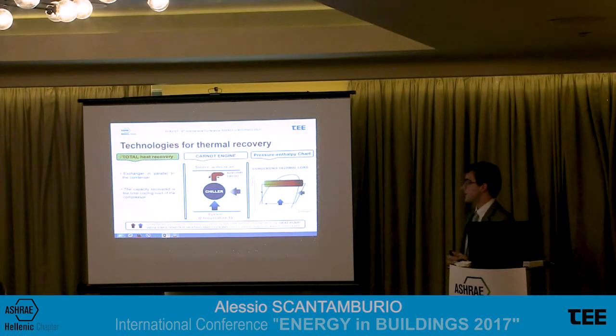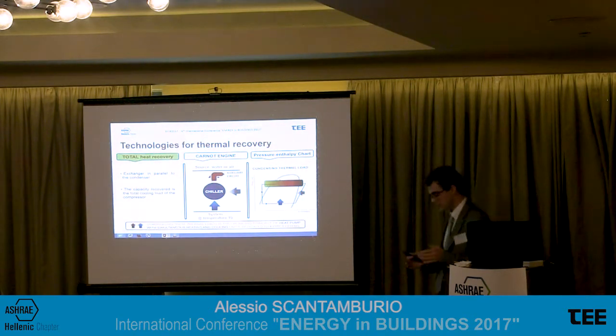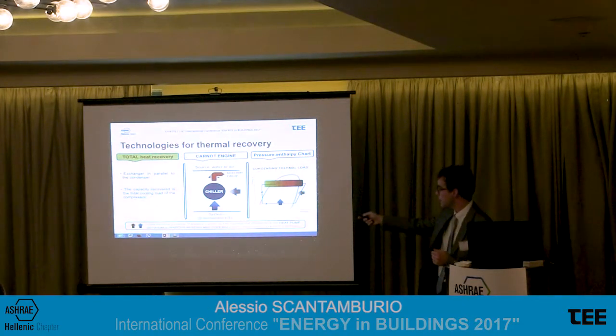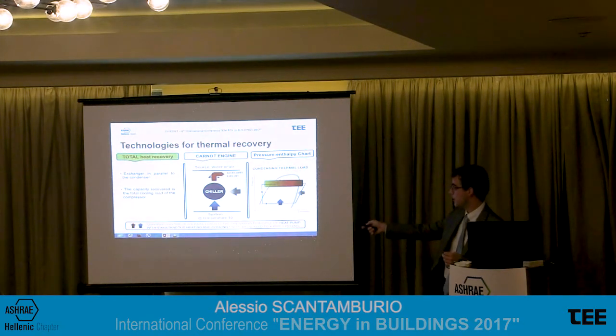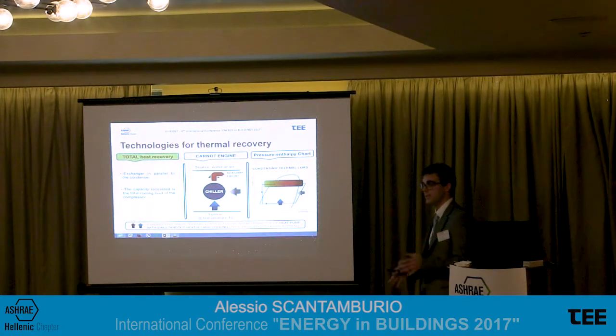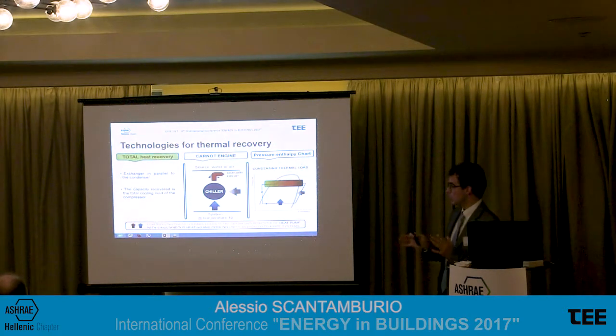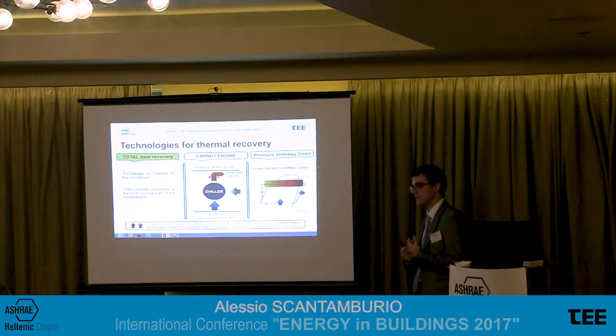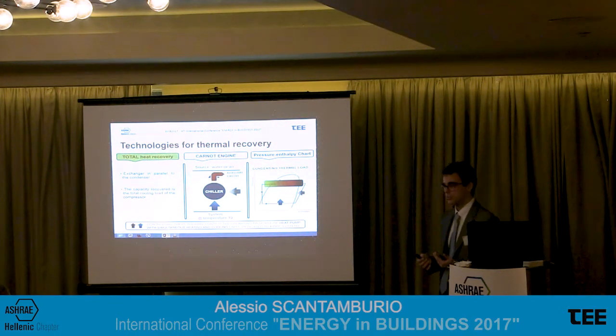Second possibility, chiller with total heat recovery. In this case, we have an additional exchanger placed in parallel to the main condenser, so we are able to recover the total condensing thermal load, still with the chiller producing cold water. The capacity recovered is the total cooling load of the compressor because we are diverting all the refrigerant flow inside this additional exchanger. So these two technologies are good and allow us to have a certain production of hot water while we are producing cold water.